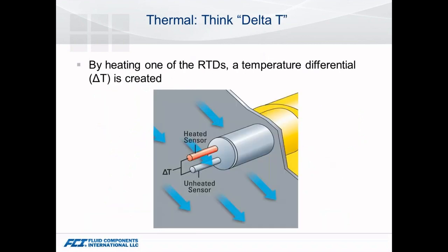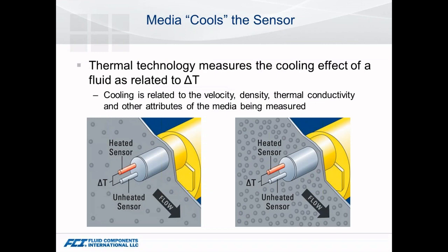Thermal technology is essentially creating a temperature differential — you think Delta T a lot of times. We have a heated sensor where we're putting current into either a heater or a self-heated RTD, comparing that to an unheated sensor and looking at that temperature differential. From that differential, we look at the cooling effects of the sensor — how that cooling is related to the velocity, density, and thermal properties of any media, whether liquid or gas.